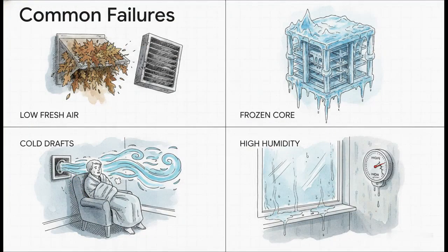You can specify the most advanced mechanical hardware on the planet, but without strict operational protocols, it will rapidly fail. Execution is everything. As professionals, we have to anticipate and troubleshoot these common operational failures. If a system is running but providing little to no fresh air, you're likely dealing with blocked exterior hoods or severely clogged filters. In cold winter conditions, condensation inside the unit can actually freeze, creating a frozen heat exchange core that completely blocks the exhaust stream. If your occupants are complaining of cold drafts, it's almost always a signal of a blocked return stream or, again, a frozen core. And persistent high indoor humidity usually points right to humidistat calibration errors or just insufficient system runtime.